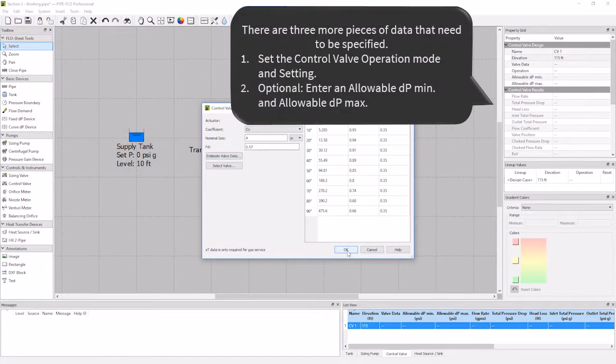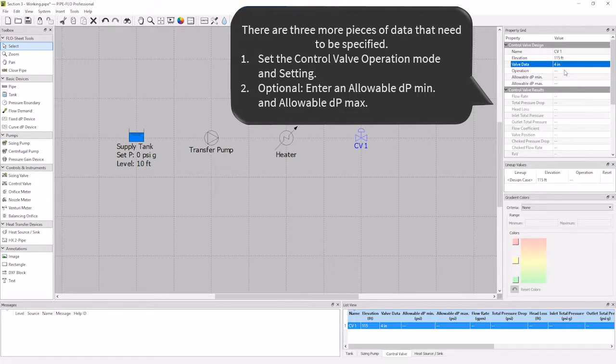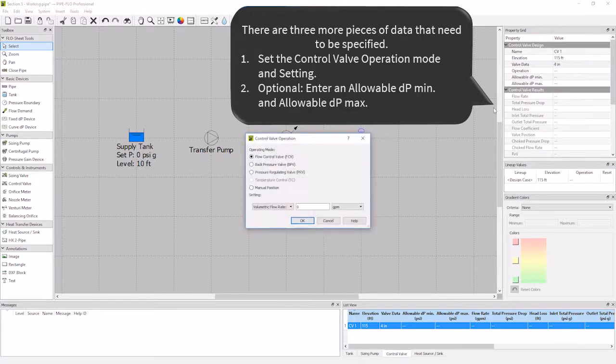The last few things to specify are the valve operation, and the allowable dP min and max. For operation, my valve is operating in a manual position of 75% open, so I will click the ellipses button to open the dialog. I'll set it to manual position, and specify 75%.